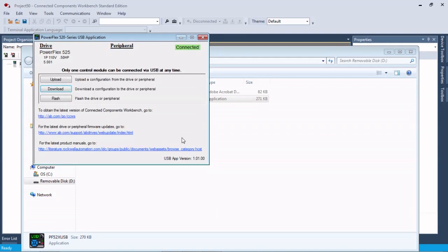What you would need to do now is take that control module, put it back onto a power module, and power up the power module under full power, 240 or 480 volt, whatever the drive is rated for, and it would load those parameters.